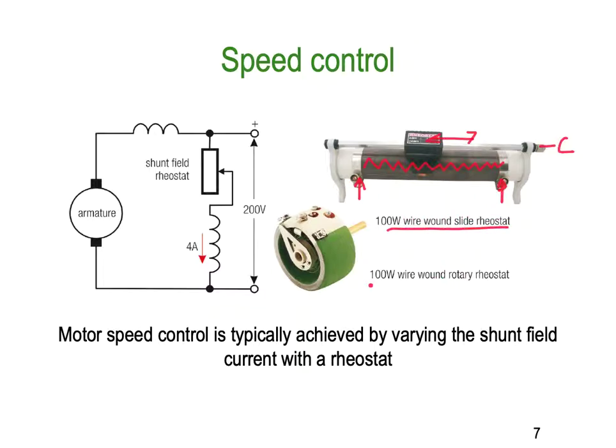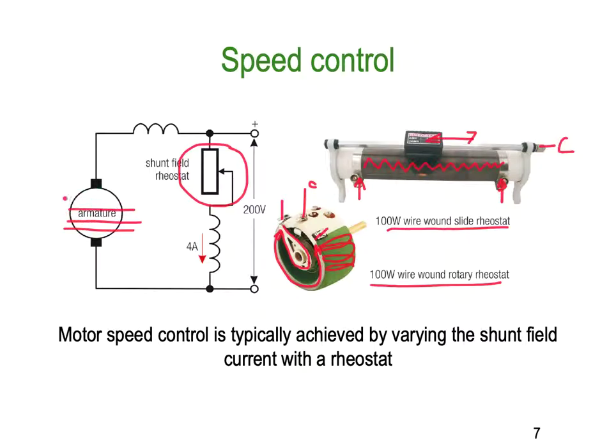You can also get a 100-watt rotary wound rheostat. Again, we've just got the wires wrapped around the side of it — hundreds and hundreds of these. There's a terminal at one end of the resistor, a terminal at the other end, and here's the common connected to this rotating arm. As the arm moves around the track, it's effectively switching in different amounts of the resistor, and you can slide that backwards and forwards in any direction you want. That becomes this field device — we're controlling the voltage drop across the field and therefore the current through the field to adjust how much magnetic flux there is across our armature.